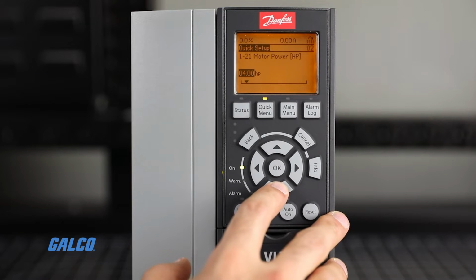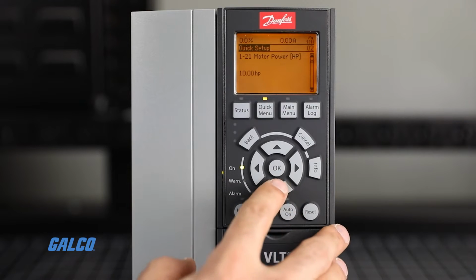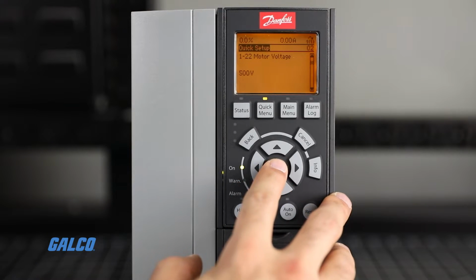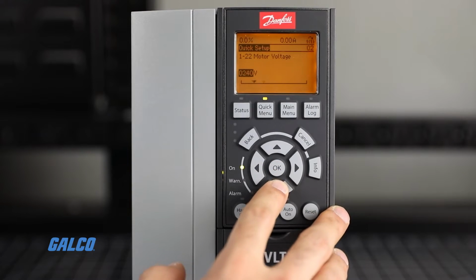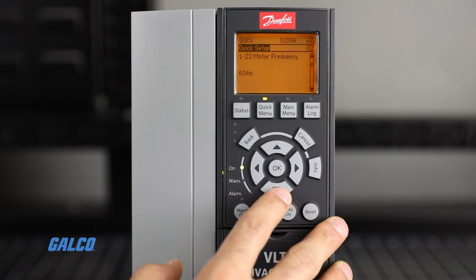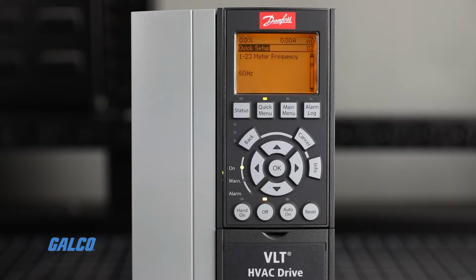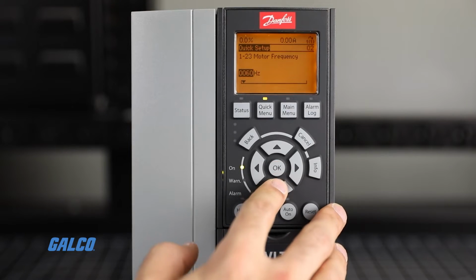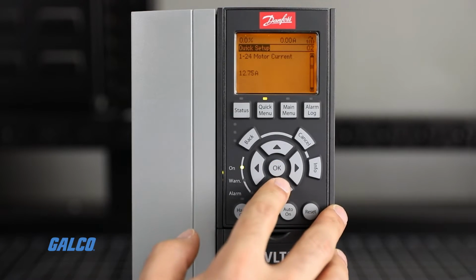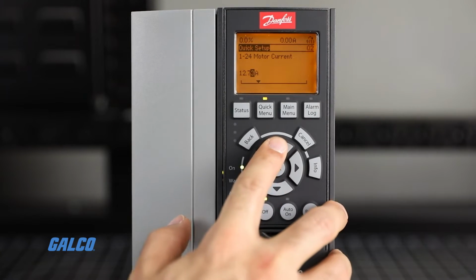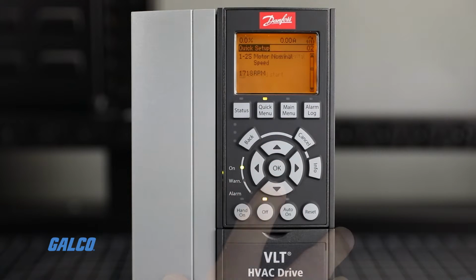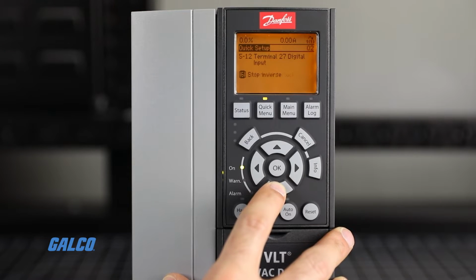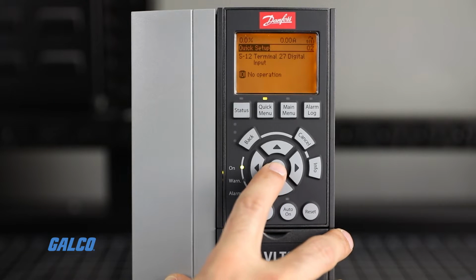You can find the motor power in horsepower on the motor nameplate if you don't know already. Next, you will enter the motor voltage at parameter 1-22. This value is found on the motor nameplate. Repeat this process for motor frequency, 1-23, motor current, 1-24, and motor nominal speed, 1-25. These values are all found on your motor nameplate. Next, parameter 5-12, terminal 27 digital input, should be set to 0, no operation.